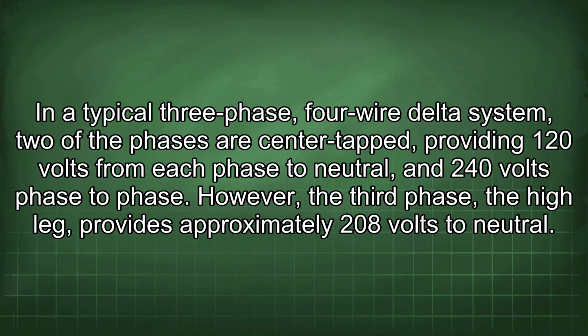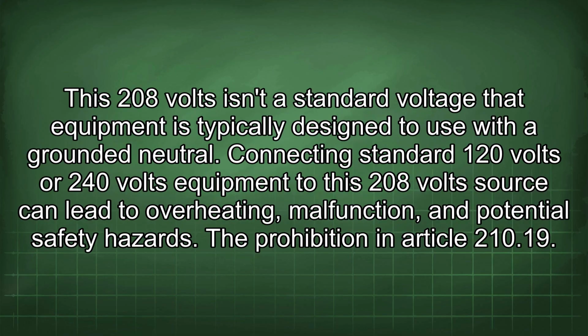The main reason behind this regulation is the voltage imbalance inherent in this type of system. In a typical three-phase, four-wire delta system, two of the phases are center-tapped, providing 120 volts from each phase to neutral and 240 volts phase to phase. However, the third phase, the high leg, provides approximately 208 volts to neutral.